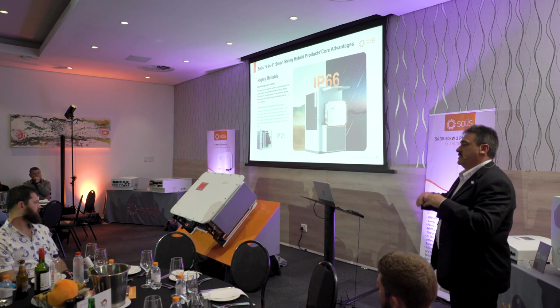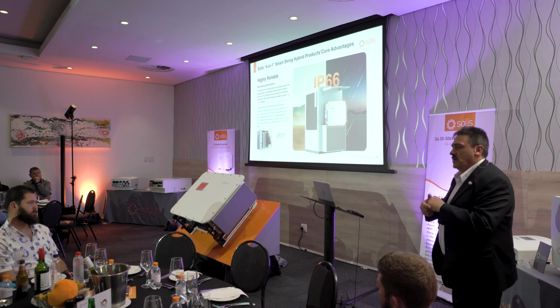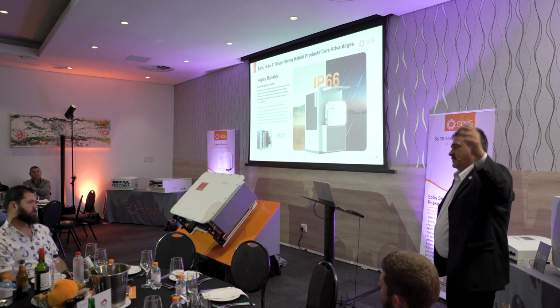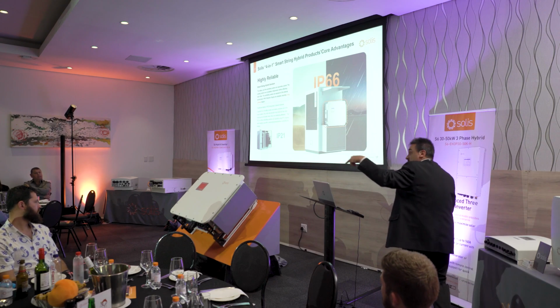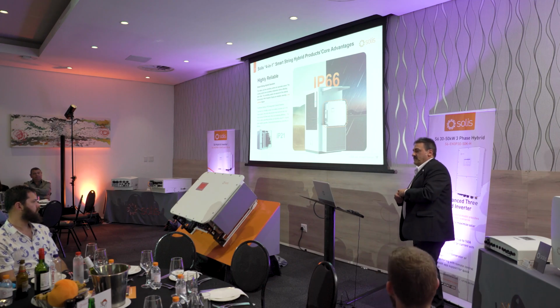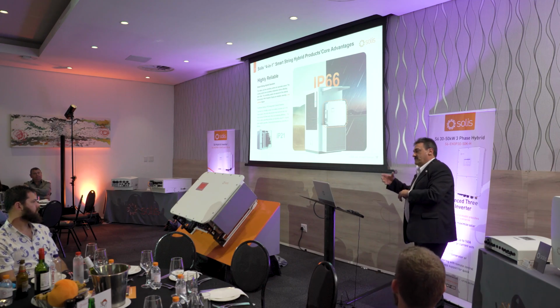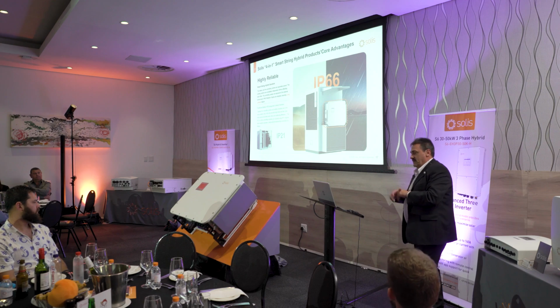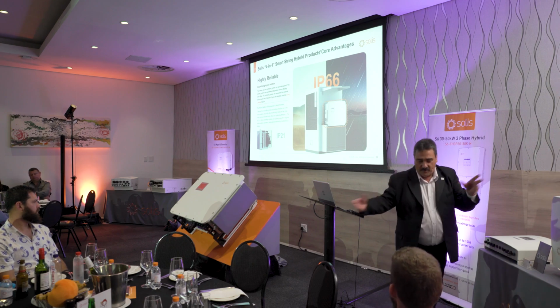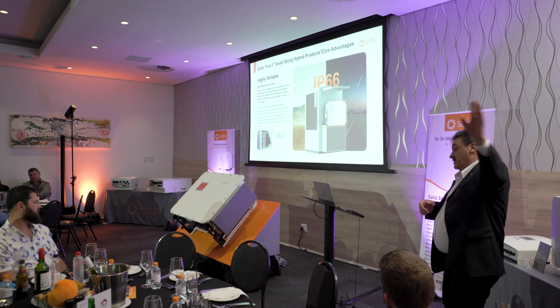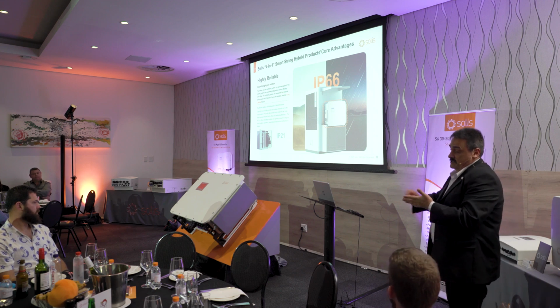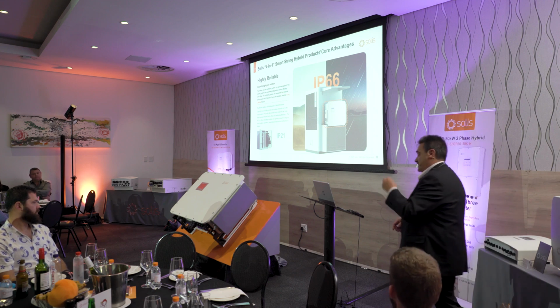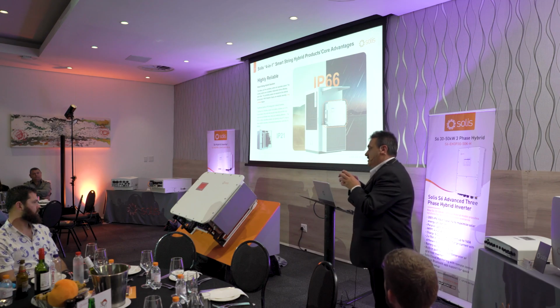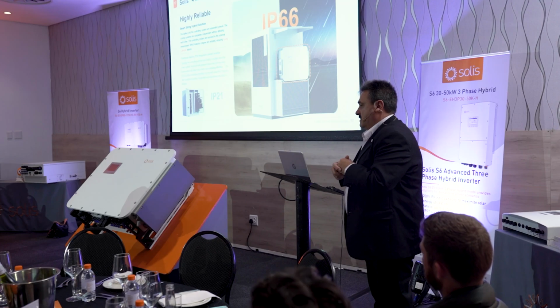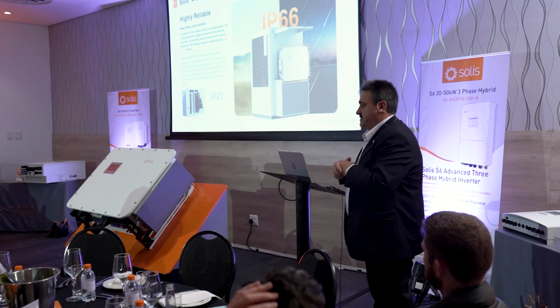I don't know if anybody ever worked in the hazardous area field. I built a lot of boxes years ago for places like Shell, Engen down here, Sasol, Natref and Petro SA, and those boxes have to be tested. You have to draw a vacuum from them, and they have to pass a very rigorous test. And even so, once it's installed, some master installation electrician has got to go there and certify that it has been installed in accordance with the IP ratings required for that installation. If the gland is not tightened or whatever, it fails.